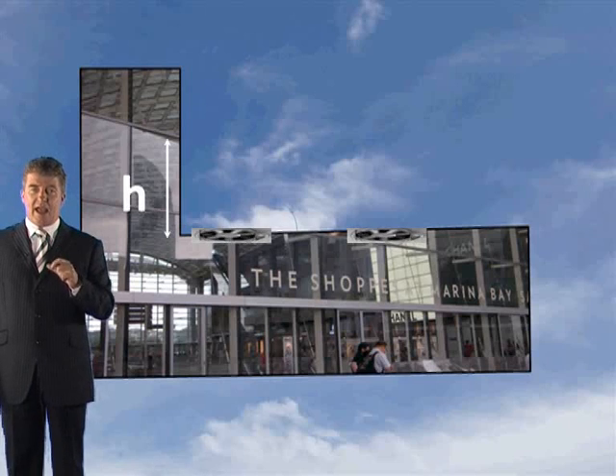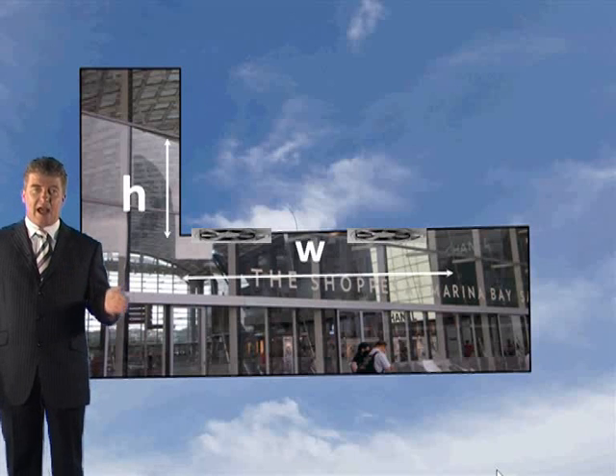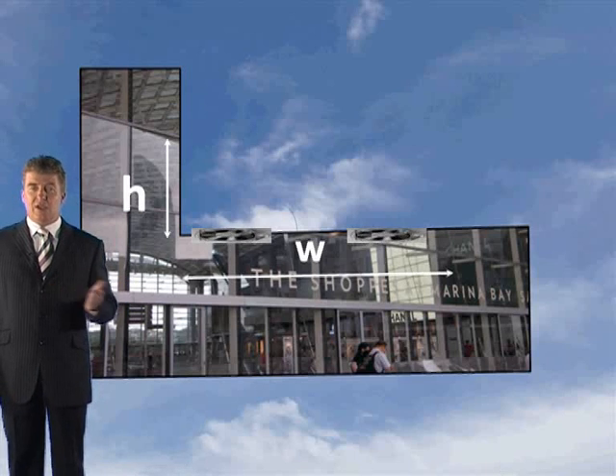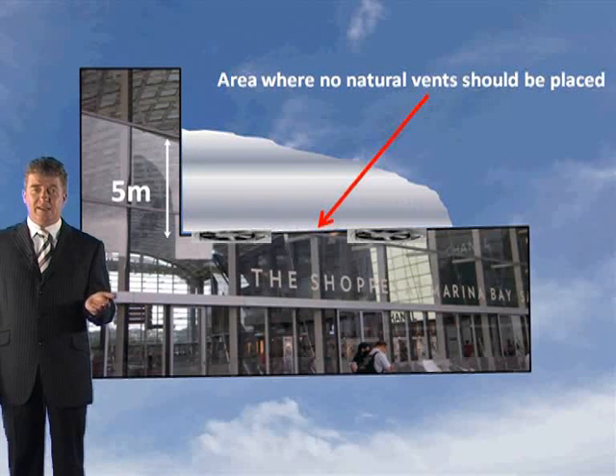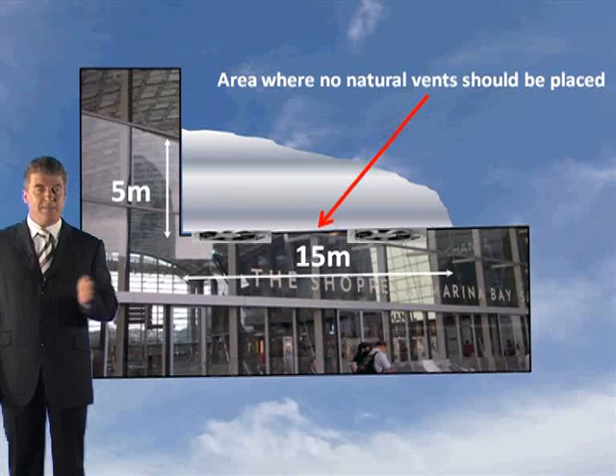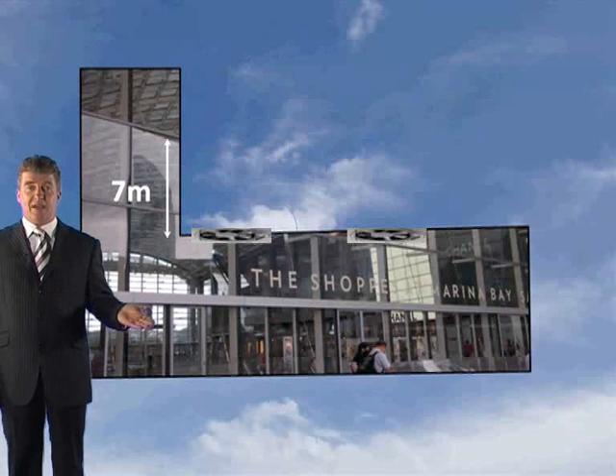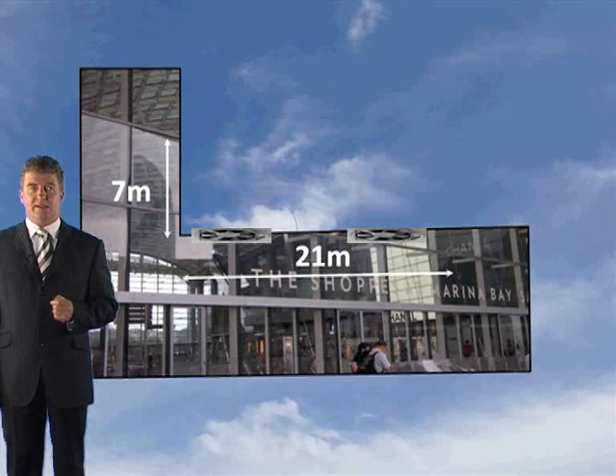So what are the rules? Well, it's generally accepted in the industry that you should not locate any natural ventilators within a distance of 3 times the height of the building. As you can see here, wherever that height is, you shouldn't locate any natural ventilators within 3 times that height. So if the height of the building here was 5 metres, then no natural ventilators should be located within 15 metres of that edge. If it's 7 metres, then you've got 21 metres.